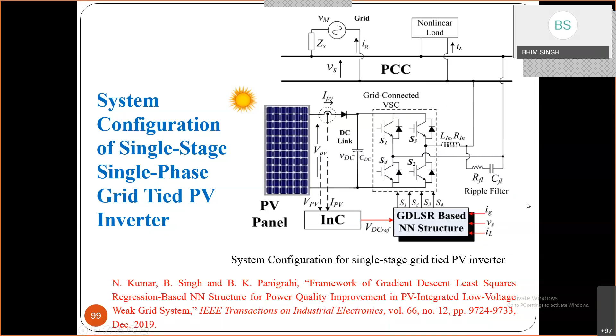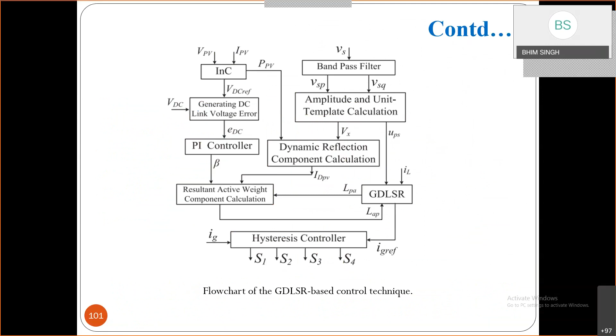You may not be taking any current, but you won't be putting current back either. Even for 24 hours, you can meet the requirements of the nonlinear load, other than active power also. One is improving the power quality, and at least we can recover the cost of the converters here. We are not changing anything except the control. The hardware is the same, but by only modifying the control, we are able to use the converter more effectively for 24 hours. We modified the control of this inverter with a proper control algorithm. As I told you, you can have even a single stage system with MPPT, sensing this and doing all the jobs.